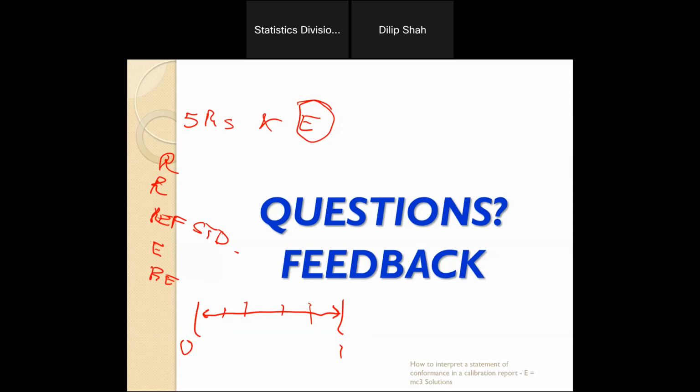You know how you use the instrument, and then you should monitor yourself in between the calibration interval, those intermediate checks, to decide how appropriate it is. Now, there's a lot of advantages to this, because if your equipment is stable, you can obviously increase the calibration interval, or if the equipment is unstable, you can shorten the calibration interval.